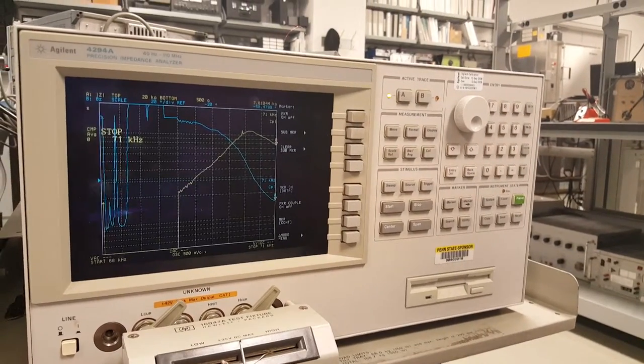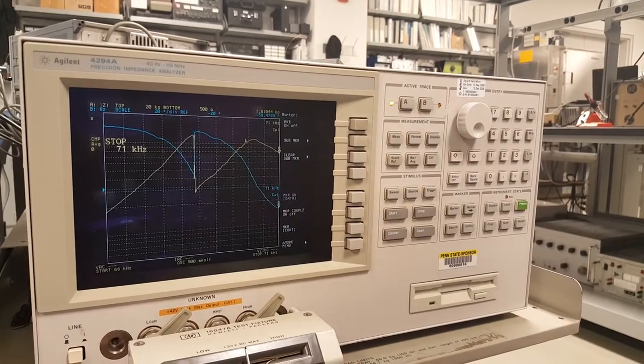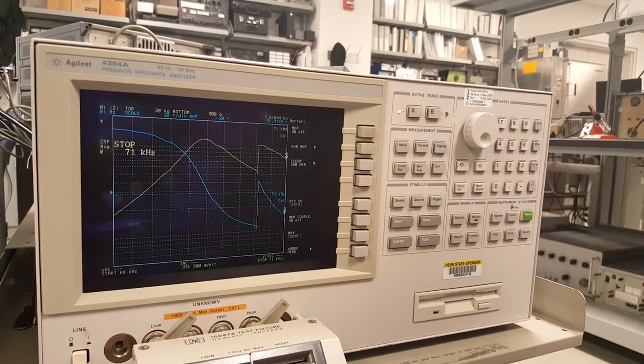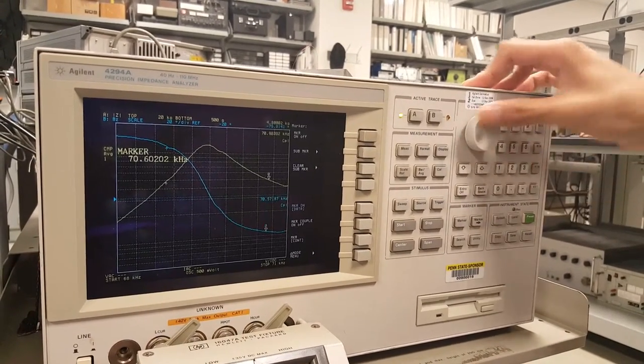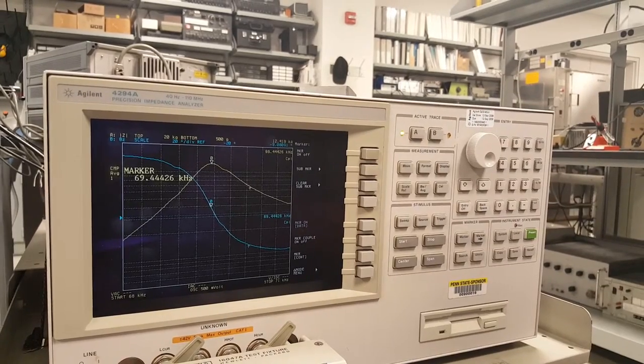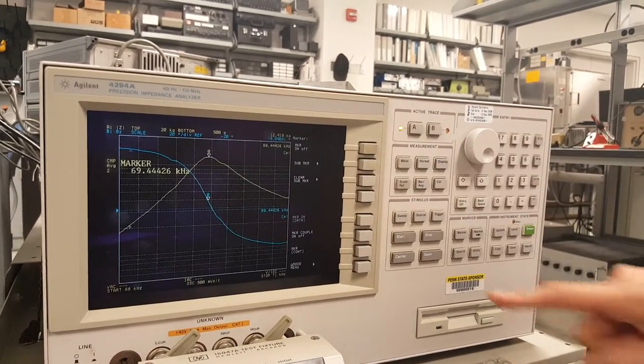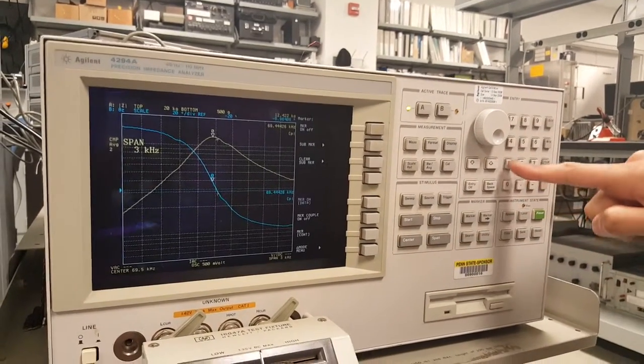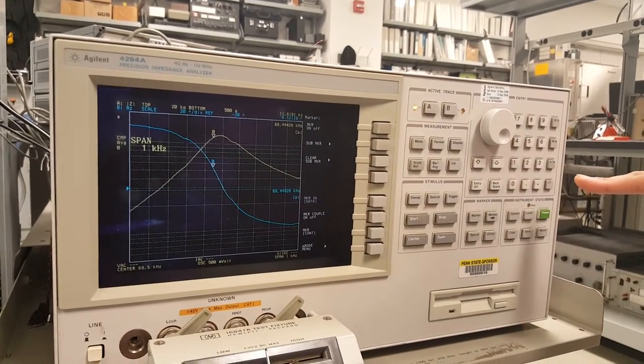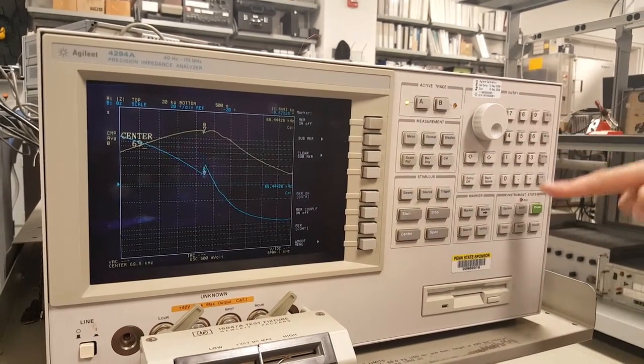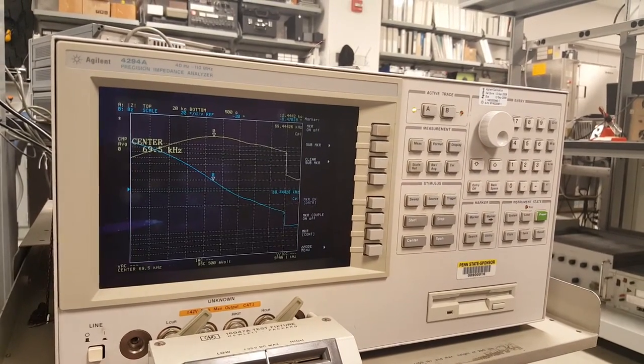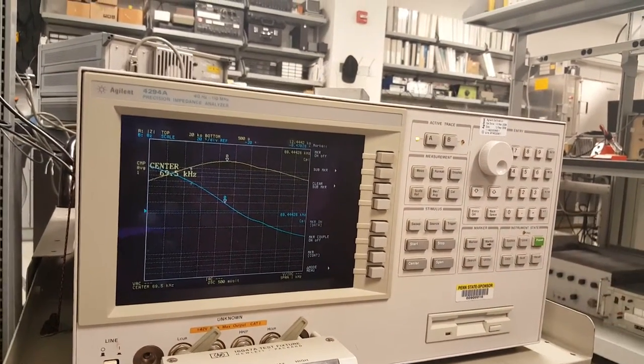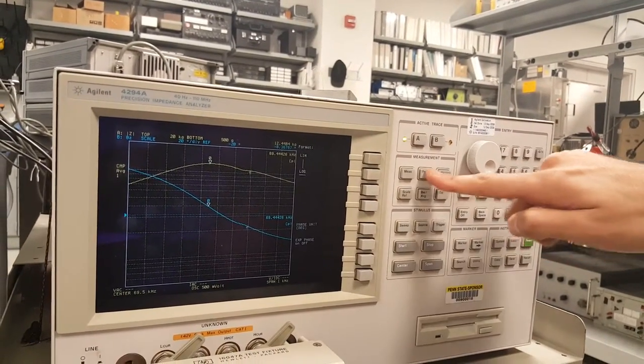And the other way, we don't quite get there. 68.8 and this is 69. So let's just go to 71. So let's start from 68 kHz. This is going to be a problem. 68 kHz and stop at 71 kHz. And we'll try to get closer now. And then we'll use this marker to get closer. We can try to do span. Span 1 kHz. The center 69.5 kHz. Now it's doing it a different way. The center point. And now we're defining a center point and a width.